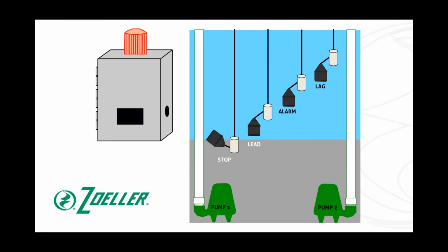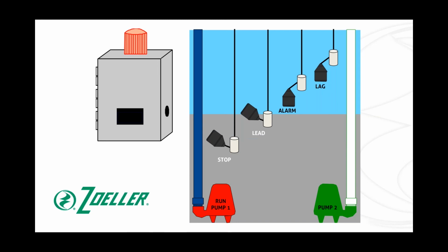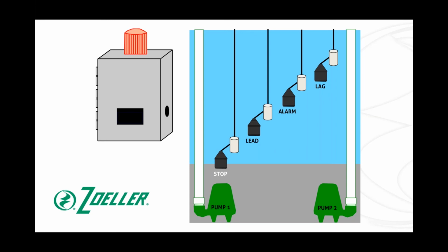So water level begins to rise. Stop float comes up. Nothing happens. Water level increases some more in the pit. It reaches our lead float. Pump 1 is activated. Pump 1 begins pumping the water out of the pit. The lead float drops out. Our stop float drops out. And we are now back to a normal water level. We're ready for the next pumping cycle.